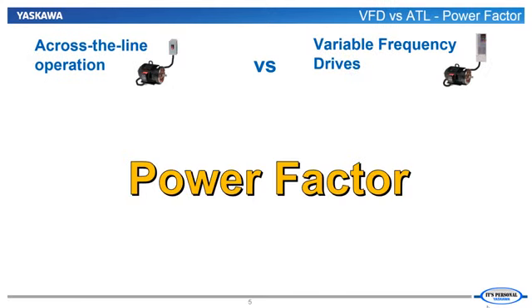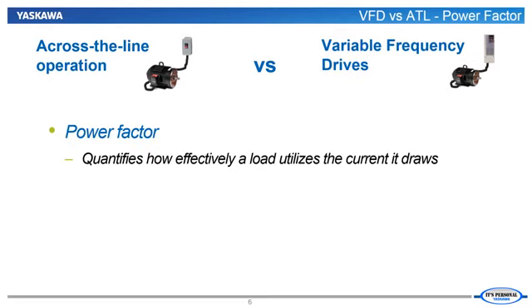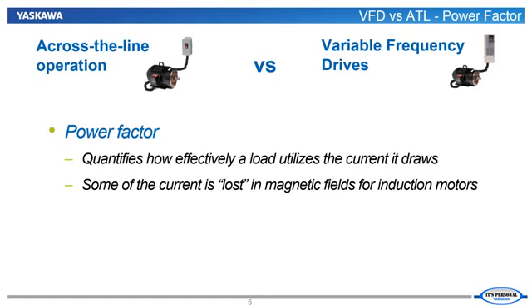The first issue we will consider is the power factor of a fan or pump application when using either a VFD or an across-the-line starter. We will try to use a familiar visual aid to understand the ups and downs of power factor. Power factor essentially designates how efficient the system is utilizing power. The closer power factor is to unity, the more efficient the system is using power. It turns out that some of the current does not actually generate the motor torque that moves the air or water. Some of the current is used to create the magnetic fields in the motor, which is required for the motor to generate torque. This reactive current is necessary, but doesn't directly move the load. The aim is to minimize it.